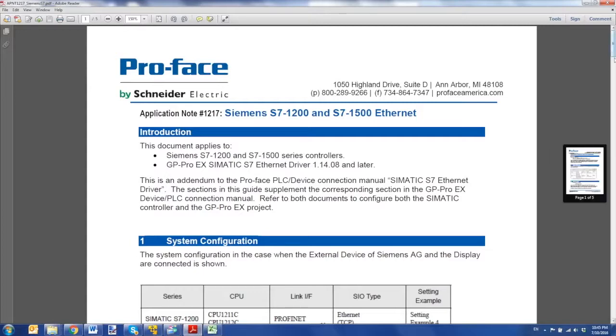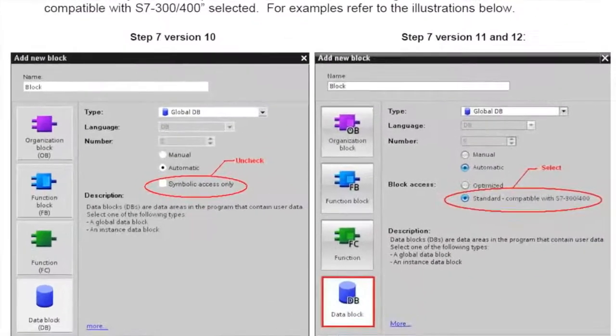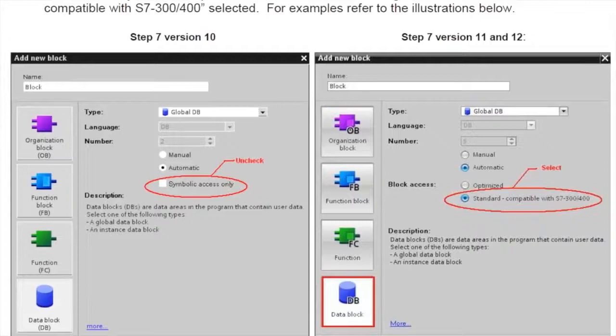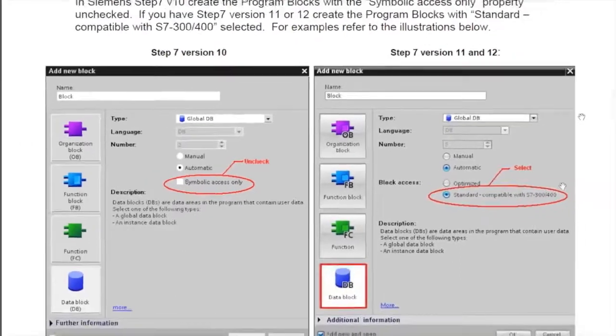This is what you need to select inside of Siemens software. You need to select standard compatible with S7-300-400, or if you're running step 7 version 10, you want to uncheck the symbolic access only.